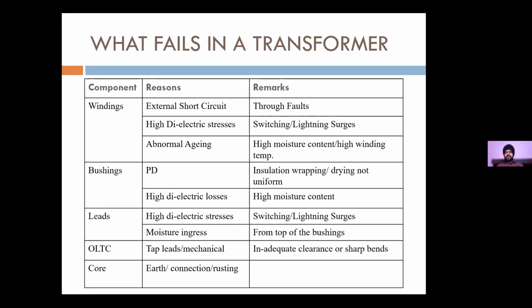Now, when we talk about a transformer failure, what actually fails in a transformer? Transformer failure can be a winding failure, which can be due to external short circuit, dielectric stresses, abnormal aging. Then bushings can also fail, due to high dielectric losses or partial discharges. Then leads, OLTC, tap leads, or mechanical damage. Then the core, due to earthing issues, multiple earthing, connection issues, or due to ingress of moisture, rusting can occur, which can cause damage to a core. So these are the major components which can fail in a transformer, which can contribute to the failure of a transformer.